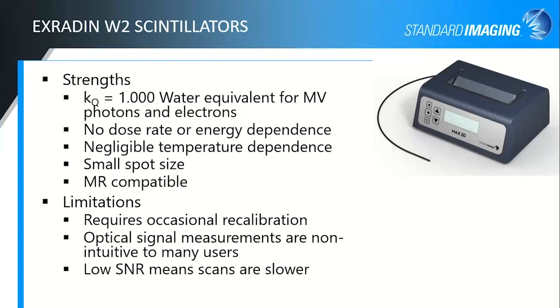So strengths anyway, the KQ is 1. If you look in that TRS 483 publication, you'll see values for the W1. The W2 is exactly the same scintillation material, so it is behaving exactly the same way in terms of that beam quality correction factor. So water equivalent for those MV photons and electrons. We've not observed dose rate or energy dependence with it. It has a very small temperature dependence, about 0.1% per degree Celsius. But if all your measurements are at room temperature, then you can ignore any sort of temperature correction as well.